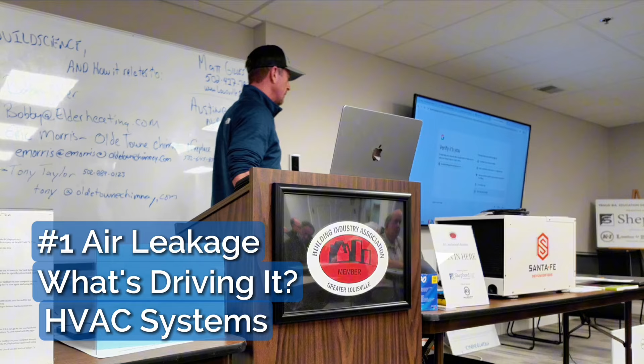And then HVAC—I don't know if the earlier speaker covered this, but a big problem in houses with comfort issues often has to do with pressure imbalances because of improperly designed or installed ductwork, or undersized ductwork. For the same amount of air that goes into a room, the same amount of air should go out of that room.